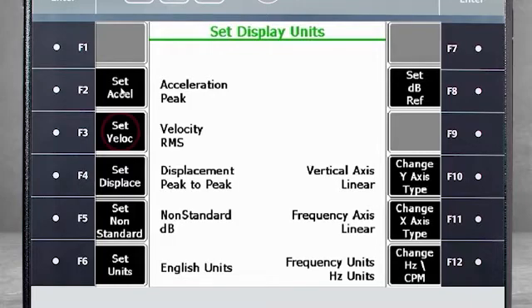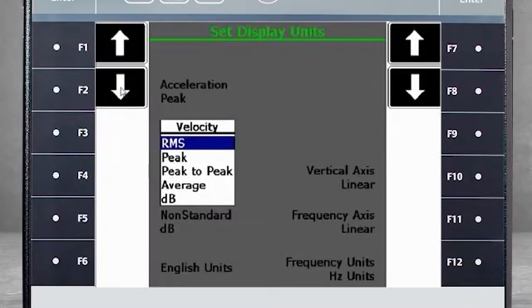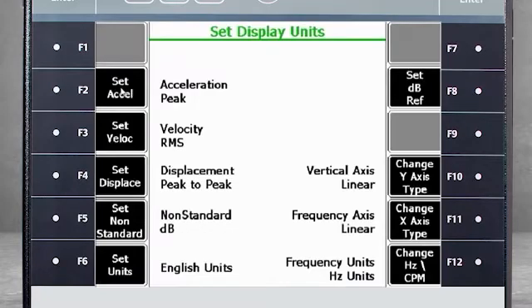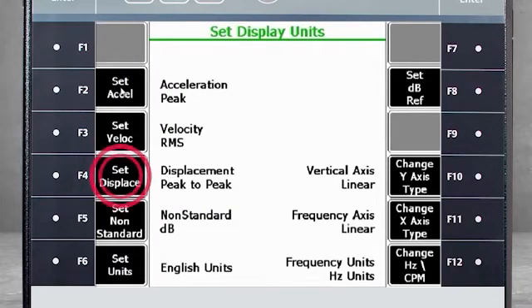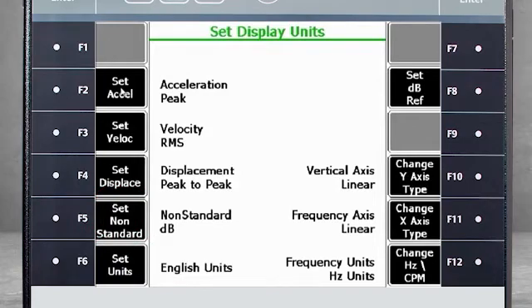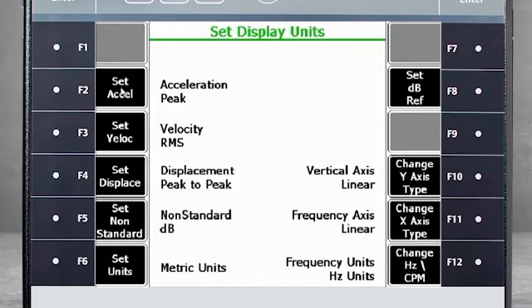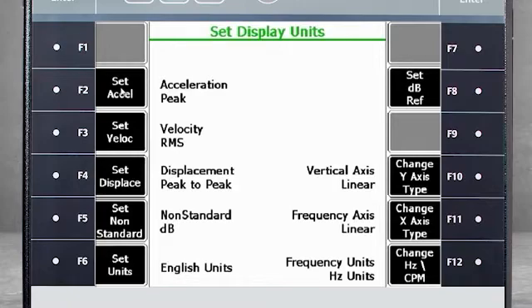Similar is true for F3 Set Velocity, where you can select from RMS, Peak, Peak-to-Peak, Average, and dB. The same is also true for F4 Set Displacement and F5 Set Non-Standard. Using F6 Set Units you can choose between English, Metric, or SI Units. And again, your changes will apply to all historical data, but can be changed back using F6 again.